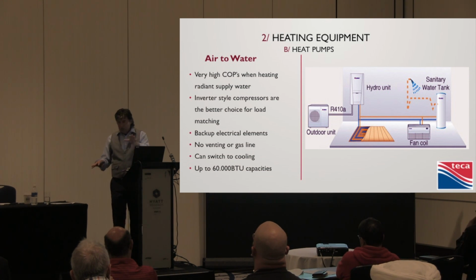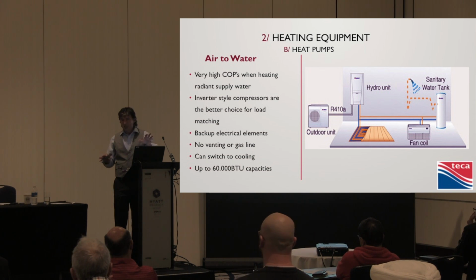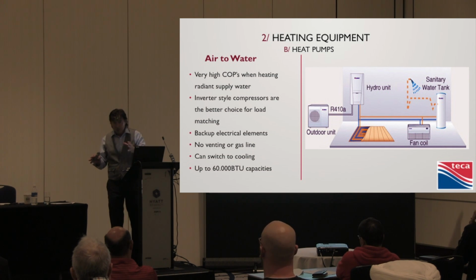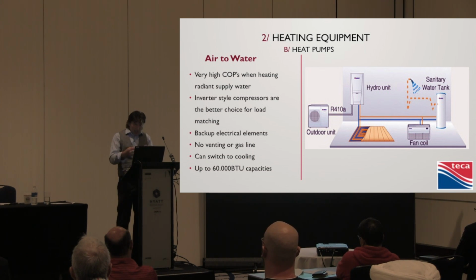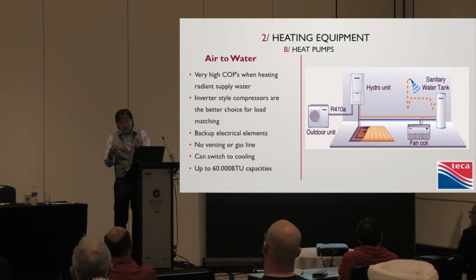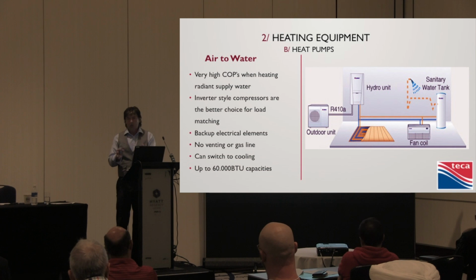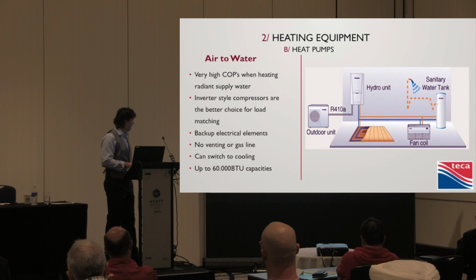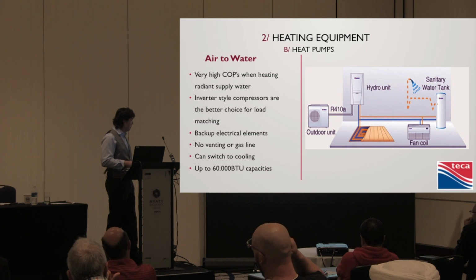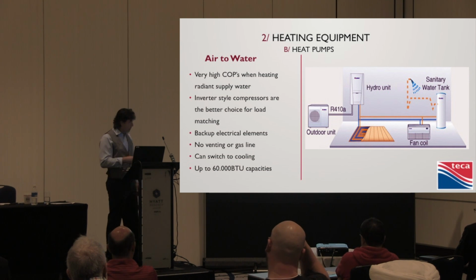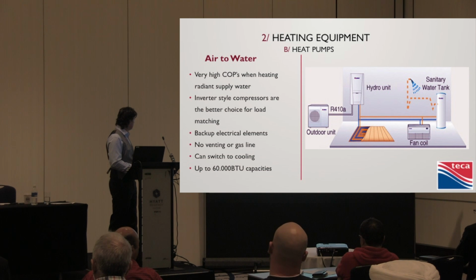But as you increase the load, it'll ramp up. So it'll match the load. So you can imagine the efficiency and reliability of that compared to Mr. 5-ton compressor. Bang, comes on, and 5 tons is too much. We're not load matching. We got 5 tons, but our load is 1.5 tons. So bang, comes on, and the short cycle shuts off. And of course, that's the hardest part on a compressor, starting and stopping. Inverter compressors have taken care of that. Super quiet. And you'll find these condenser fans, for the most part, you can just about watch them go around. So there's great manipulation of refrigerant there.